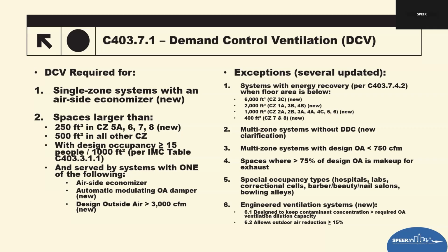These updates expand the reach of the DCV across more buildings, especially schools, gyms, offices, conference rooms, retail spaces. The intent of this is to reduce the outdoor intake while spaces are partially occupied, saving fan and heating and cooling energy. So we have already seen occupant sensors in the buildings for commercial. This is now basically basing it on a certain occupant size.